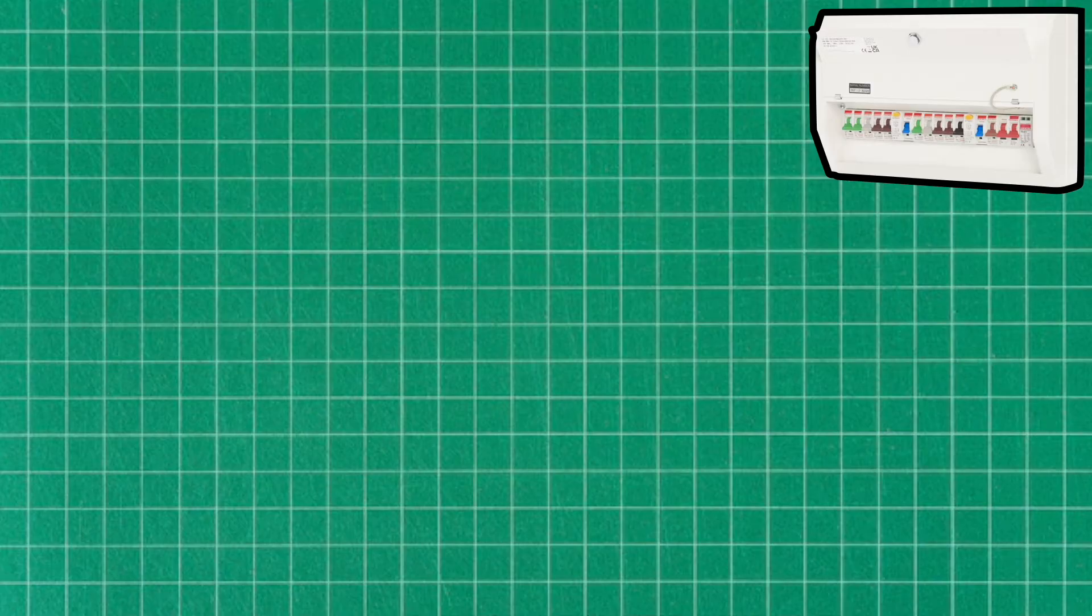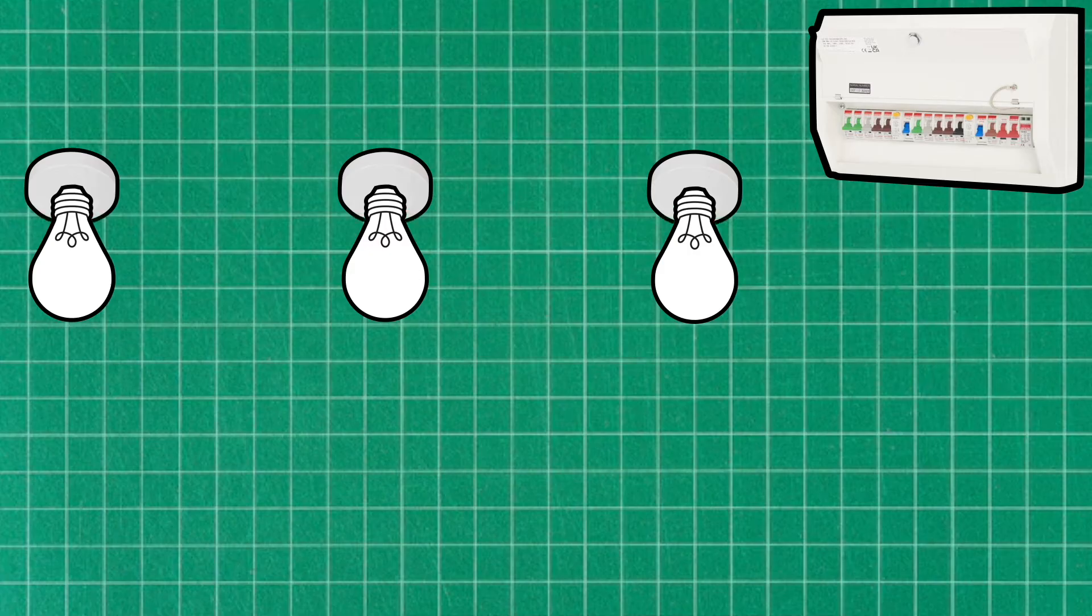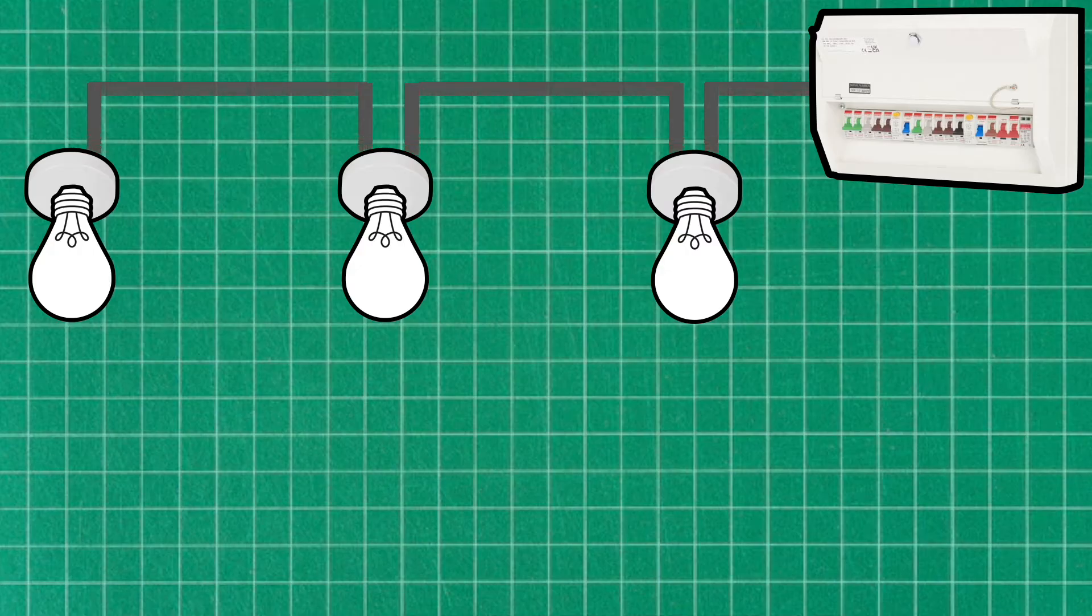So let's take a quick look at an example now just so we can understand this concept a little better. So I'm going to go ahead here and draw in a lighting circuit. At the top right of the screen I've got my consumer unit, then I've got three light pendants, and these will be wired in with basic 1.5 mil twin and earth cable. So as you can see from the graphic there, the twin and earth starts from the consumer unit and then daisy chains from one light pendant to the next. And as the circuit is radial, it finishes at the last lamp.